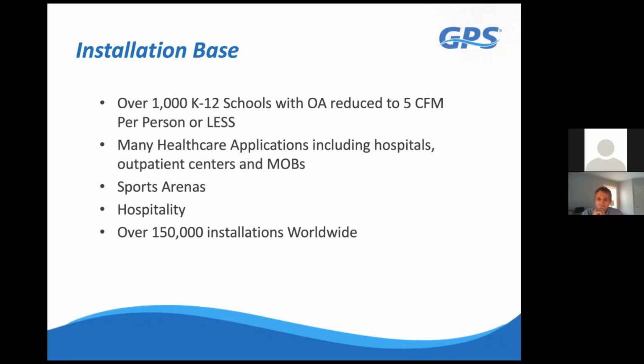So currently we have over 1,000 K through 12 schools using our technology, and a lot of the school systems are using it to reduce their outside air requirements. In healthcare applications, we're not able to reduce their outside air requirements because they're following a different set of guidelines. But in schools and non-healthcare applications, you're able to clean the air, recirculate the air, because you're using this technology to remove the contaminants of concern instead of using more outside air to dilute the contaminants.